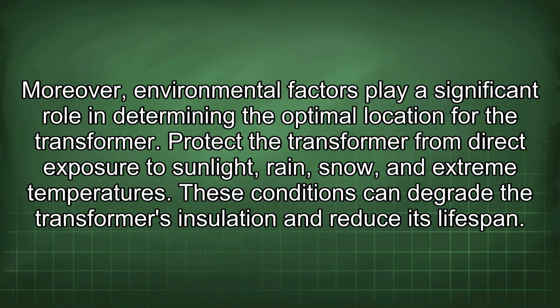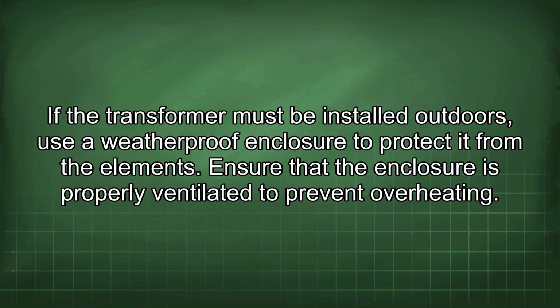Moreover, environmental factors play a significant role in determining the optimal location for the transformer. Protect the transformer from direct exposure to sunlight, rain, snow, and extreme temperatures. These conditions can degrade the transformer's insulation and reduce its lifespan. If the transformer must be installed outdoors, use a weatherproof enclosure to protect it from the elements. Ensure that the enclosure is properly ventilated to prevent overheating.